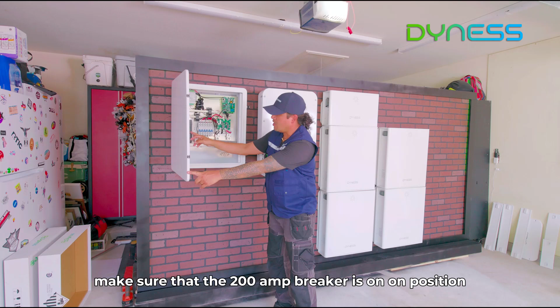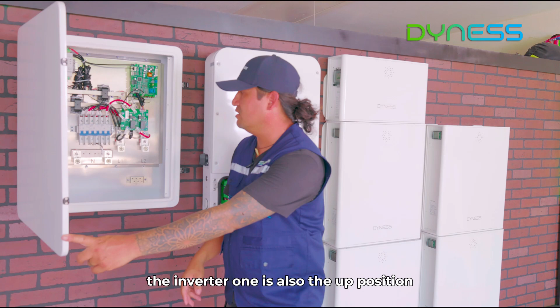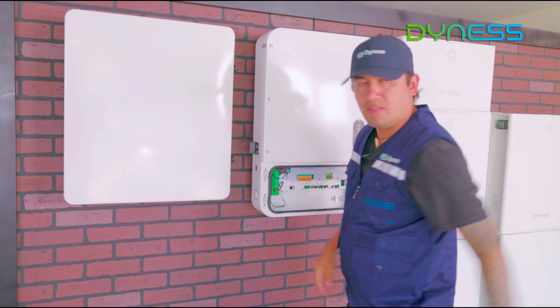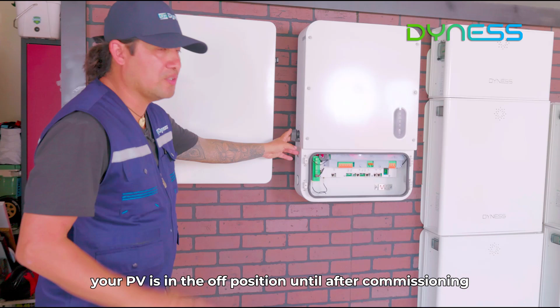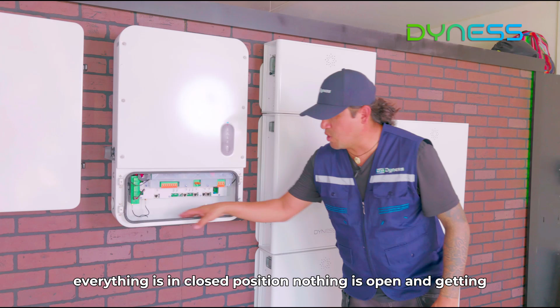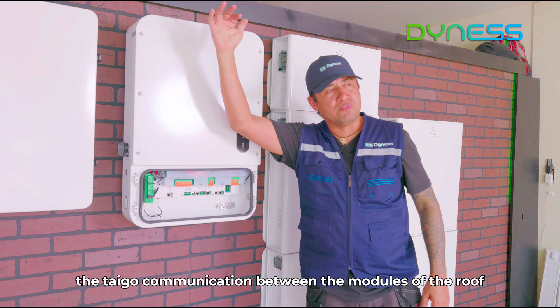The smart control device, we're going to make sure that the 200 amp breaker is in the on position, which is up. The inverter 1 is also in the up position. Everything else is terminated properly according to the NEC code. Then our next step is your hybrid inverter. What you want to make sure is that the RSD switch is on in place. Your PV is in the off position until after commissioning. You want to make sure everything is in closed position, nothing's opened and getting ready. You want to make sure all of these tabs are in the down position, meaning closed, that all the wires are good and tight. Make sure to double check all your connection points. Once all commissioned, you'll see a little green light here. That means the Tigo communication between the modules of the roof or the building is communicating here.